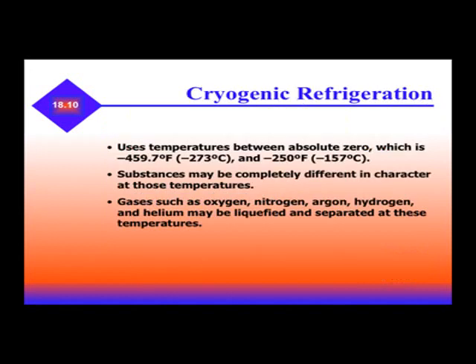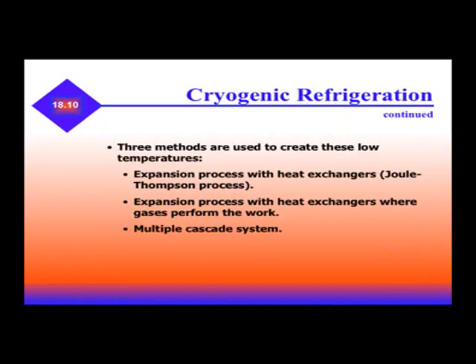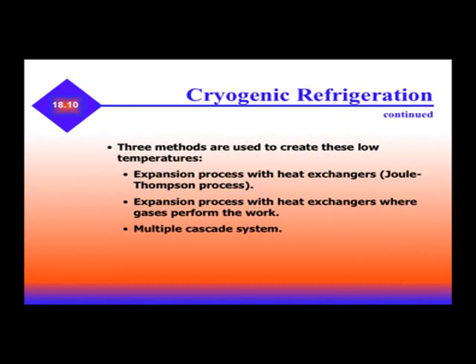Cryogenic refrigeration uses temperatures between absolute zero, which is negative 459.7 degrees, and negative 250 degrees. Substances may be completely different in character at those temperatures. Gases such as oxygen, nitrogen, argon, hydrogen, and helium may be liquefied and separated at these temperatures. Three methods are used to create these low temperatures: an expansion process with heat exchangers, an expansion process with heat exchangers and gases, and multiple cascade systems.